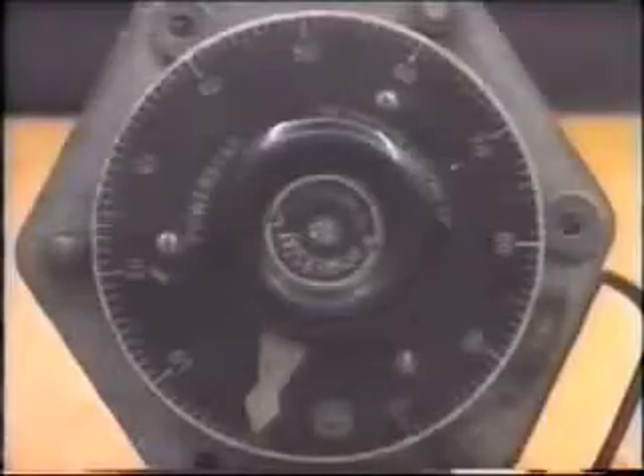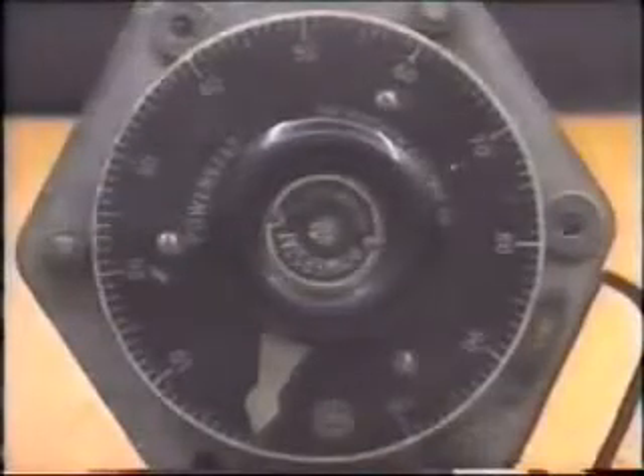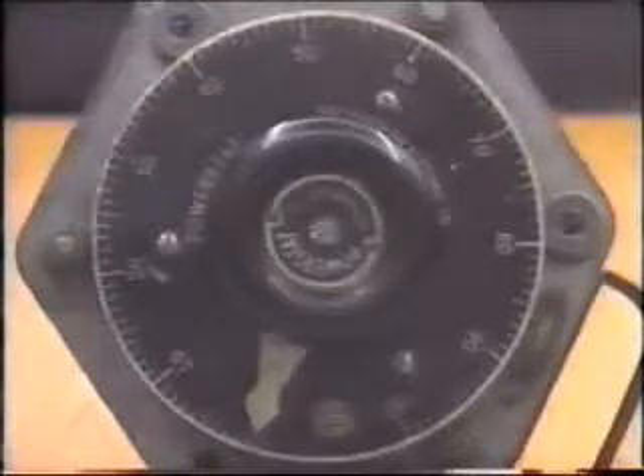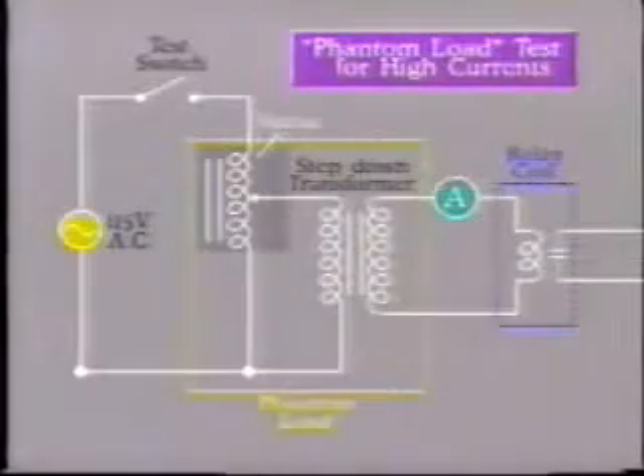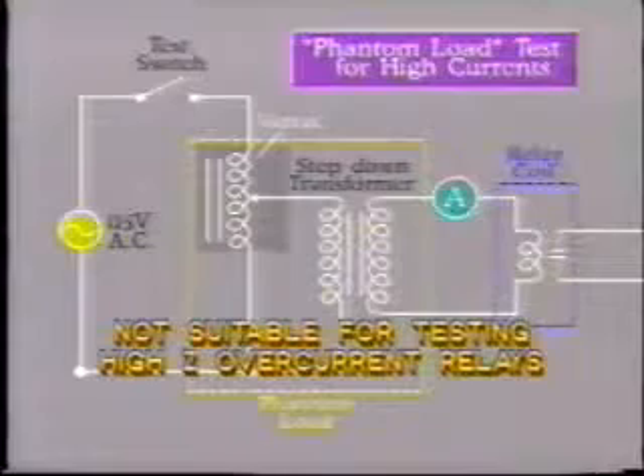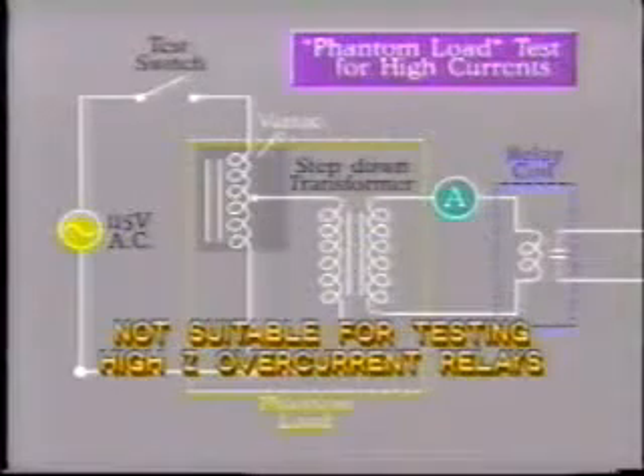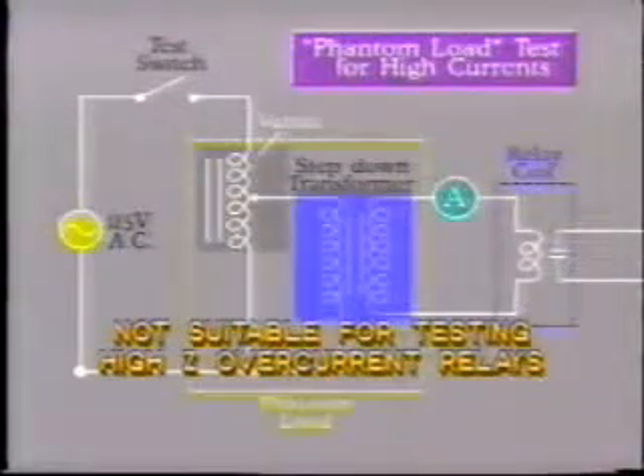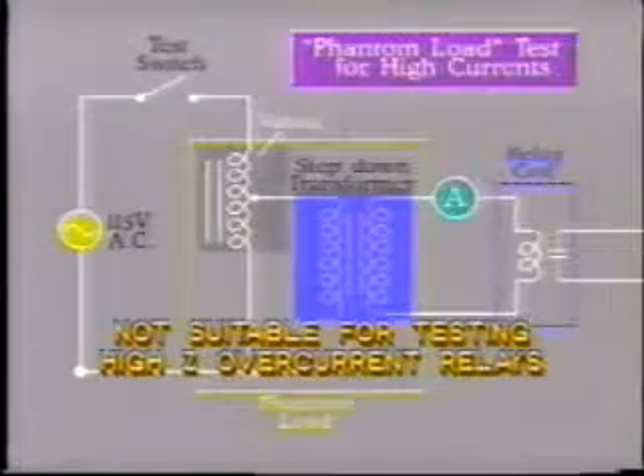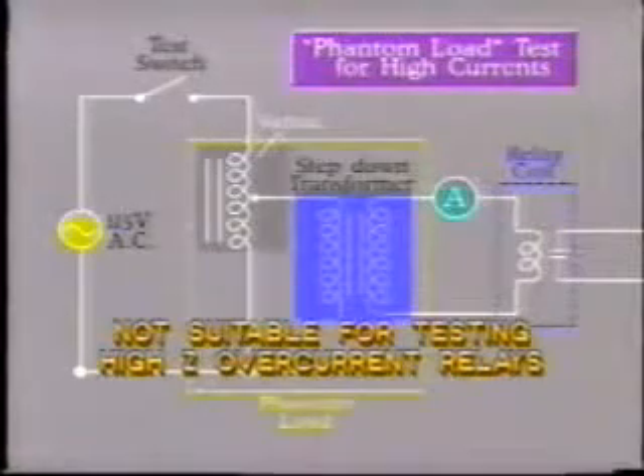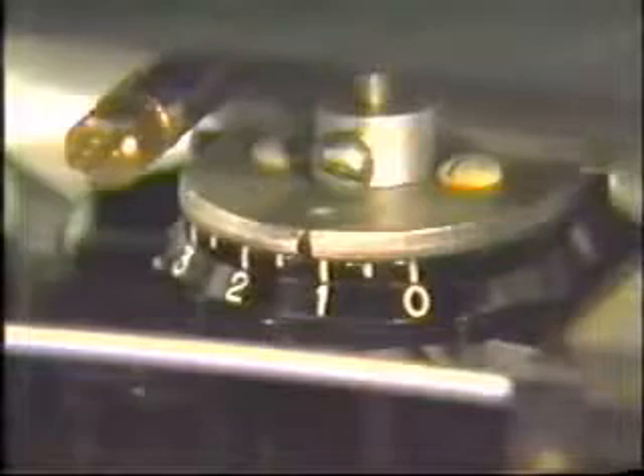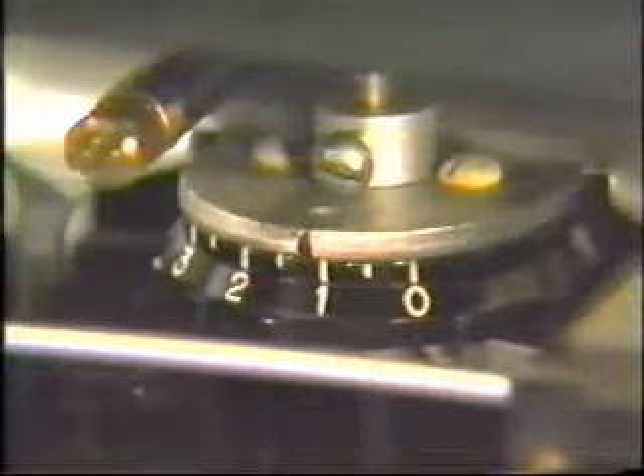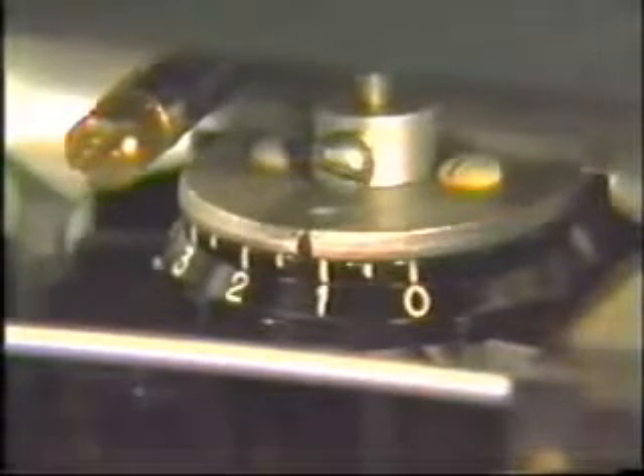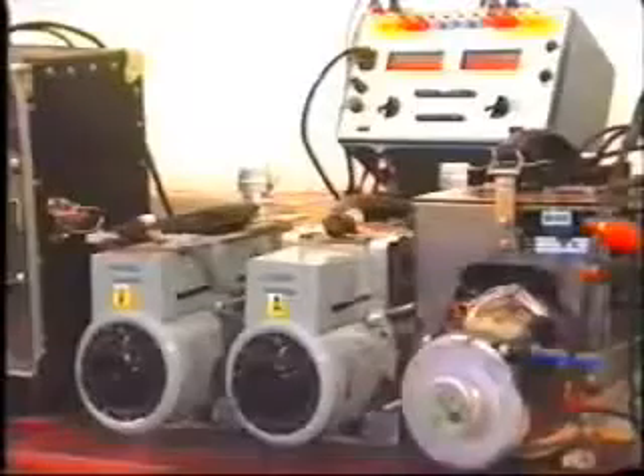An advantage of the phantom load is that it does not get overheated or consume energy like a resistor. However, take note that it is not suitable for testing high impedance overcurrent relays. This is because the step-down transformer may saturate at high test currents. As a result, the time dial could be set too low, with consequent potential for misoperation.